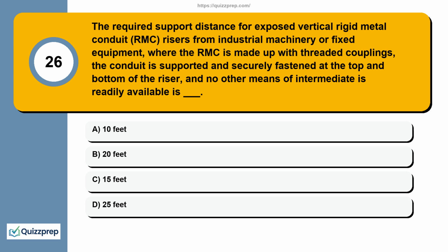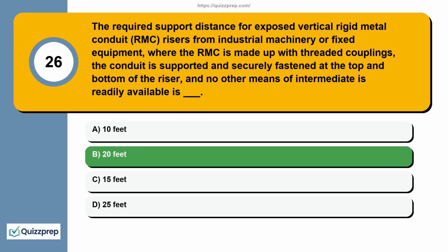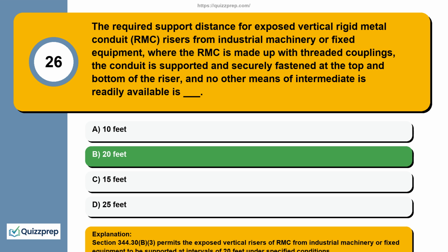Question 26. The required support distance for exposed vertical rigid metal conduit, RMC, risers from industrial machinery or fixed equipment, where the RMC is made up with threaded couplings, the conduit is supported and securely fastened at the top and bottom of the riser, and no other means of intermediate support is readily available, is 10 feet, 20 feet, 15 feet, 25 feet. Section 344.30(B)(3) permits the exposed vertical risers of RMC from industrial machinery or fixed equipment to be supported at intervals of 20 feet under specified conditions.